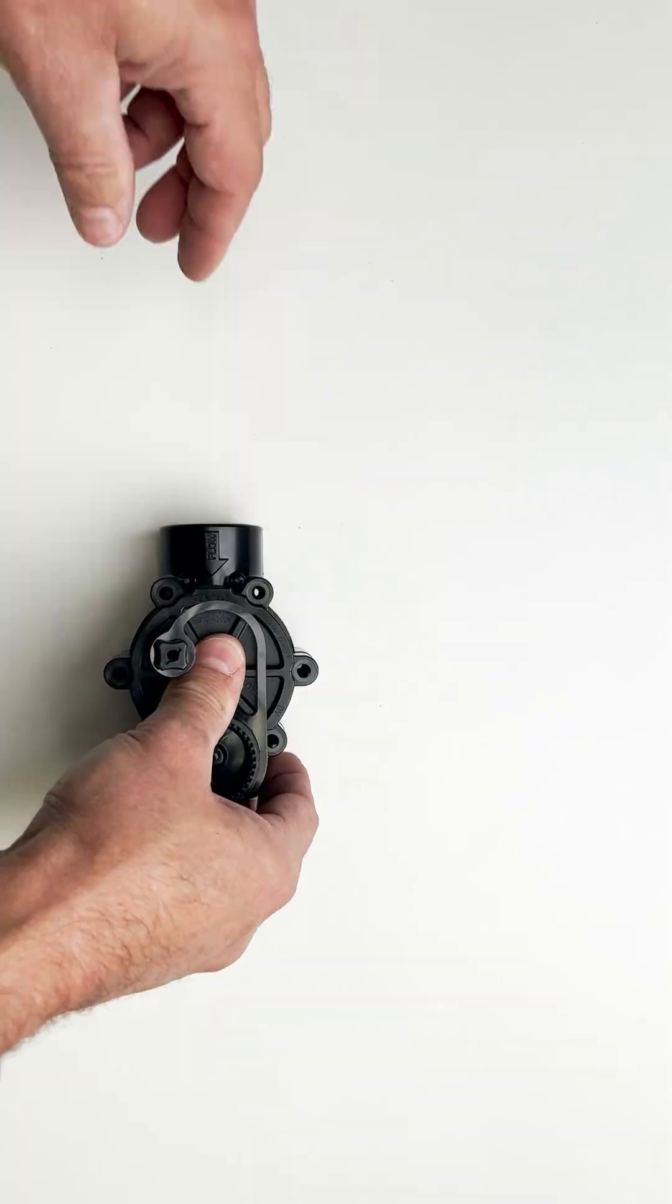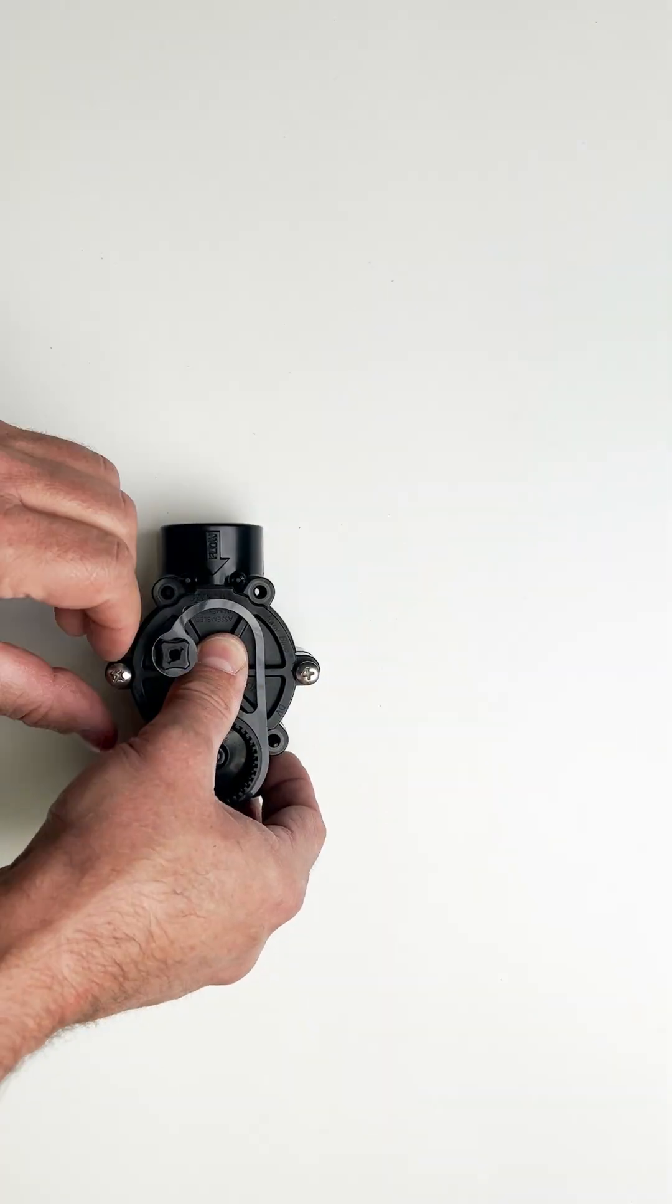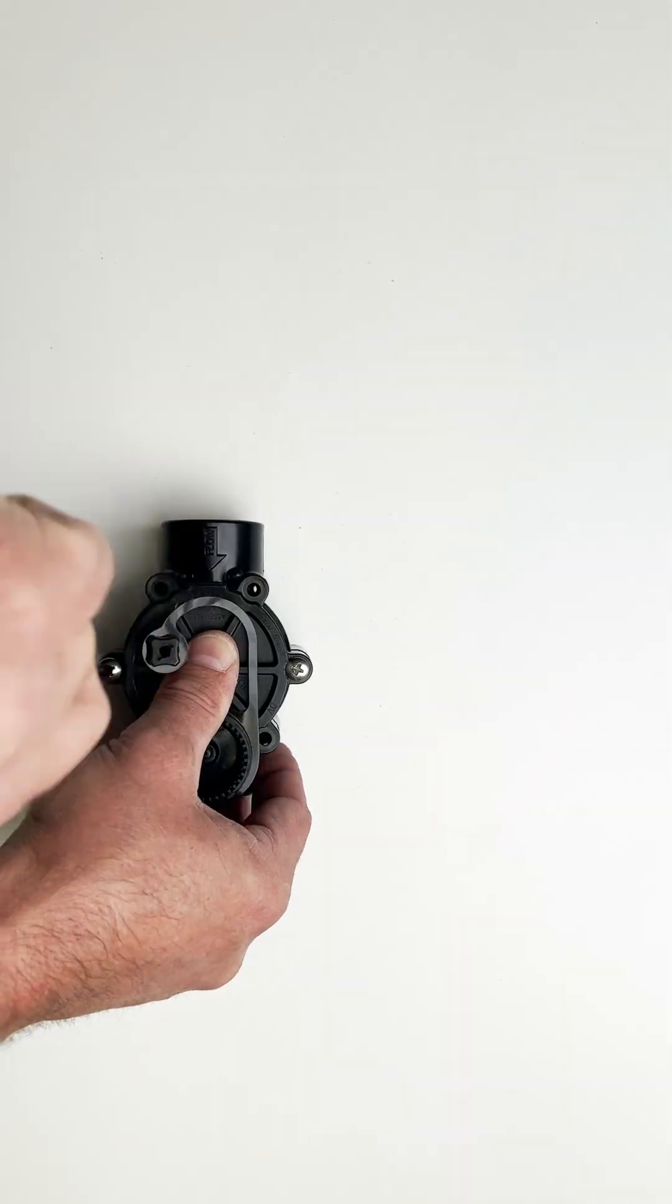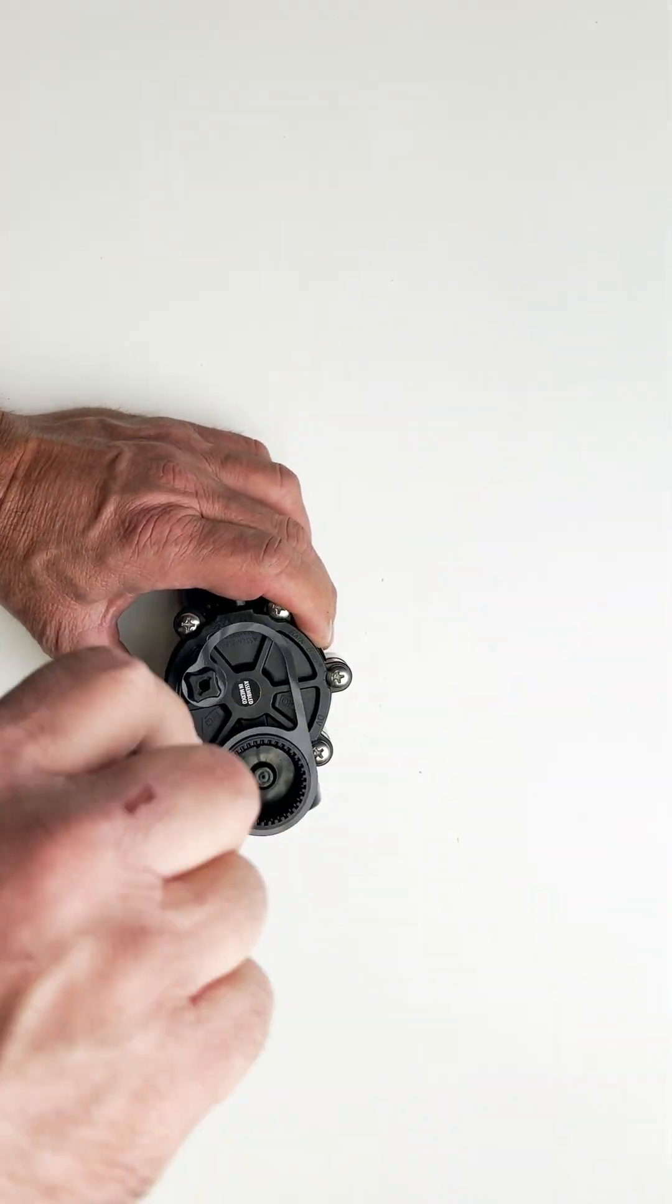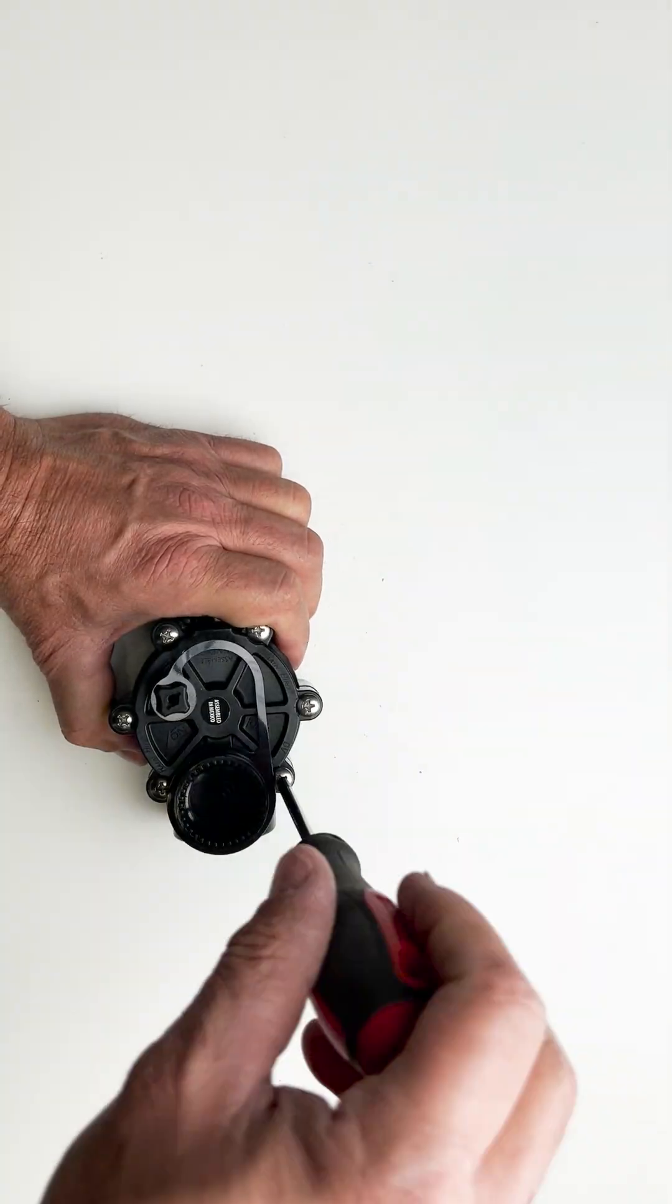Reinstall the bonnet. You'll need to hold the bonnet down while installing the screws. Wait to install all the screws before tightening them. And when you tighten them, I recommend using a crisscross pattern.